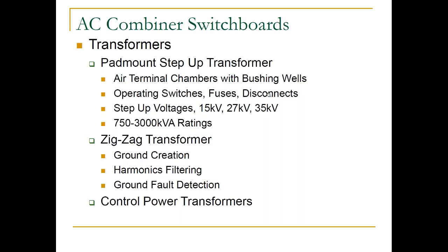Transformers, oftentimes you're going to see the pad mount step-up transformer might be at 15 kV, it could be a 25 kV, 27 kV application, and even up to 35 kV. Oftentimes it's anywhere from 750 to 3000 kVA. Obviously it depends on the size of the solar installation. Do you have a 1 meg, 5 meg, multiple different strings? What is it? A zigzag transformer, and then all of the different control power transformers.